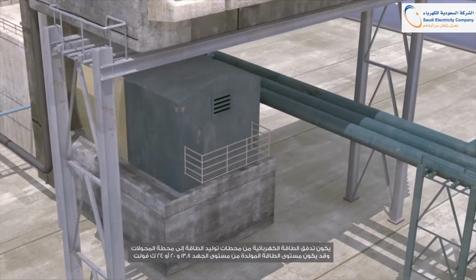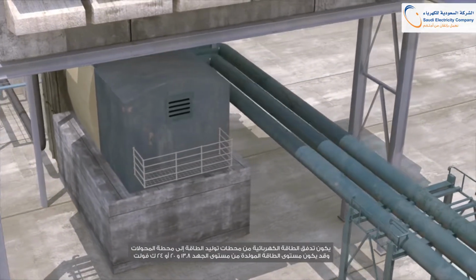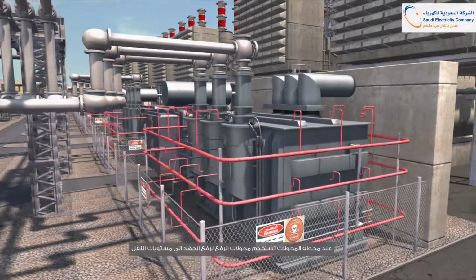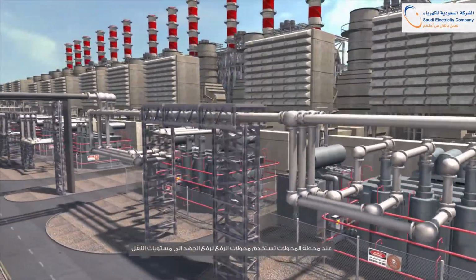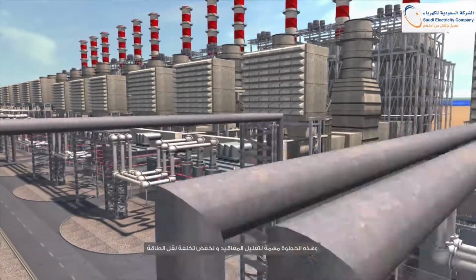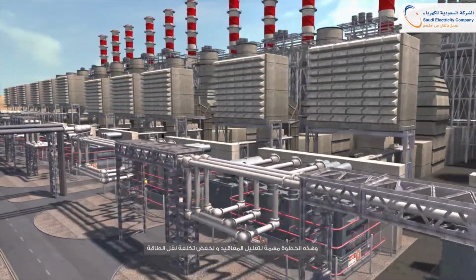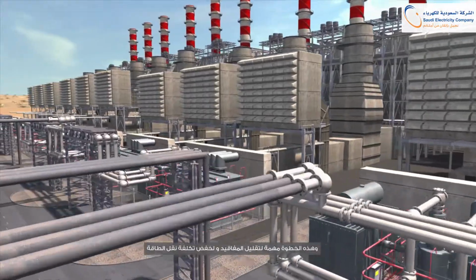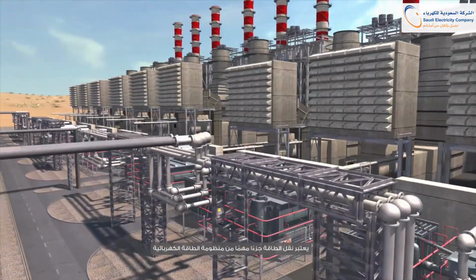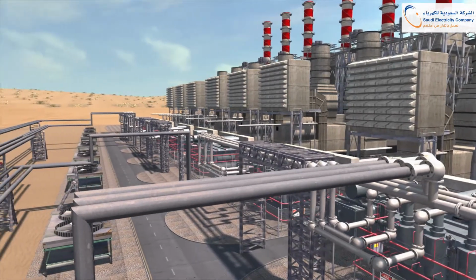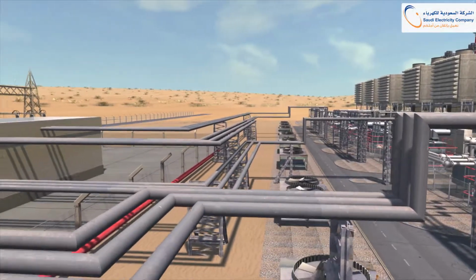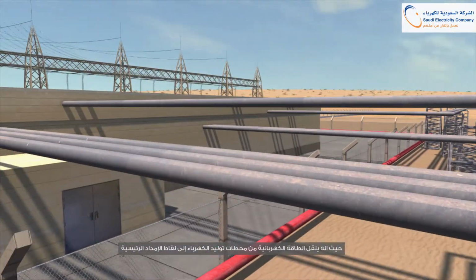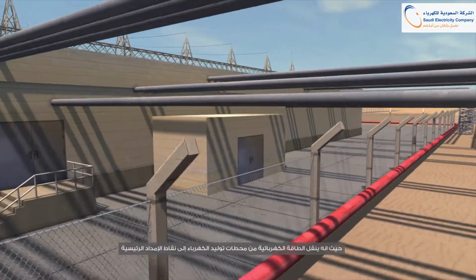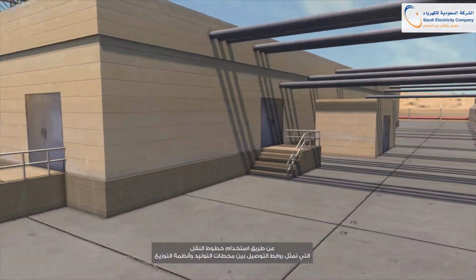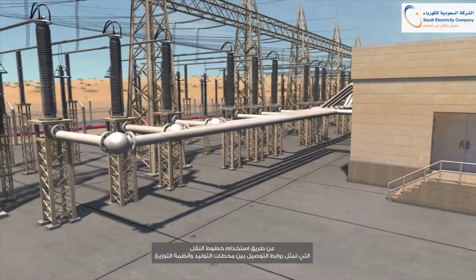The switching station that receives the generated power may have a voltage level of 13.8, 20, or 24 kilovolts. At the switching station, step-up transformers are located to raise the voltage to transmission levels. This step is essential to minimize the transmission losses and get an economical cost for power transmission. Power transmission is an important section of the electrical power system. It transfers the generated electricity from the power plants to the main supply points by using transmission lines, which are the connecting links between the generating stations and the distribution systems.